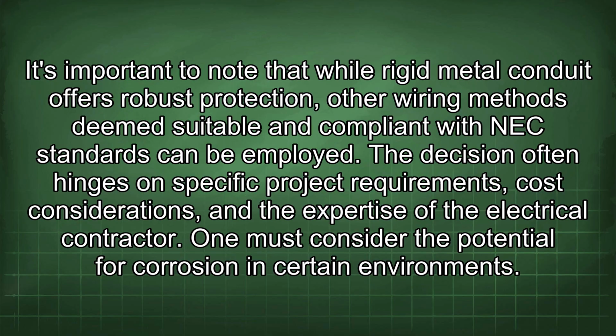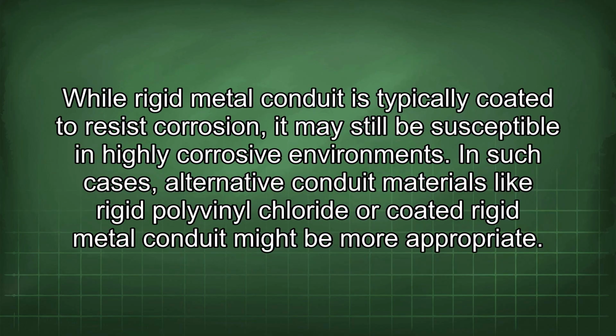One must consider the potential for corrosion in certain environments. While rigid metal conduit is typically coated to resist corrosion, it may still be susceptible in highly corrosive environments. In such cases, alternative conduit materials like rigid polyvinyl chloride or coated rigid metal conduit might be more appropriate.